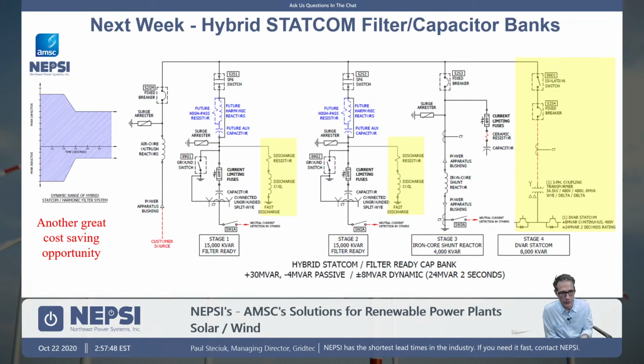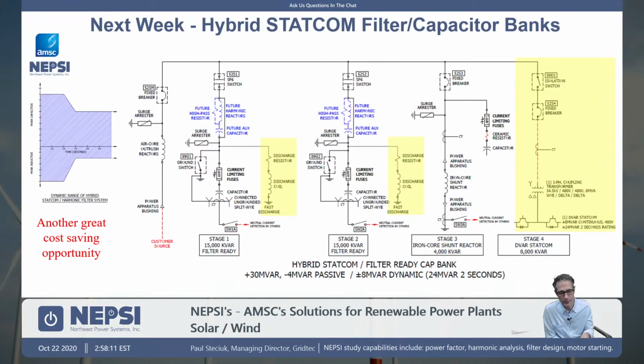So it would be an AMSC STATCOM here, and here we're showing an 8 MVAR system, which would be 2 of their 4 MVAR DVAR systems. The coupling transformer, you would still cable over to it, but we would have the breaker and the disconnecting switch within our own gear, which means that you have a single point of entry, as you see here. So a fully integrated solution. So that will be next week's Tech Talk.